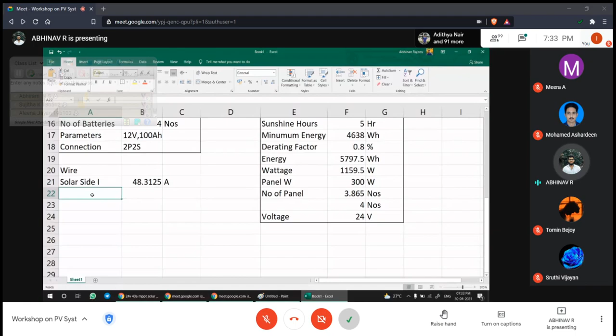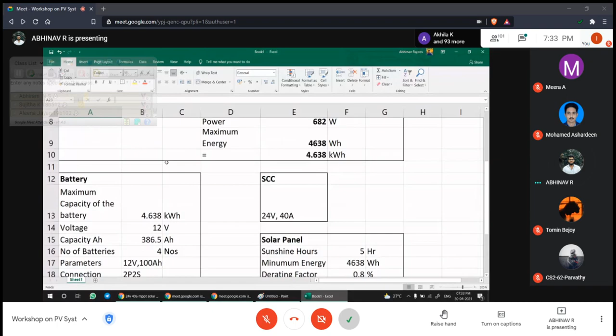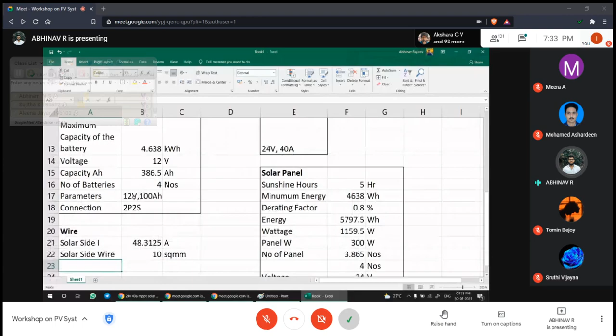Coming to the battery side, what is the maximum current flowing from the battery? It would be 700 watts divided by 24 volt. 29 amperes will be flowing through the batteries, around 30 amperes. For 30 amperes, what is the size? 5 square mm is not available, so we'll go for 6 square mm. Battery current is 30 amperes, 6 square mm wire.